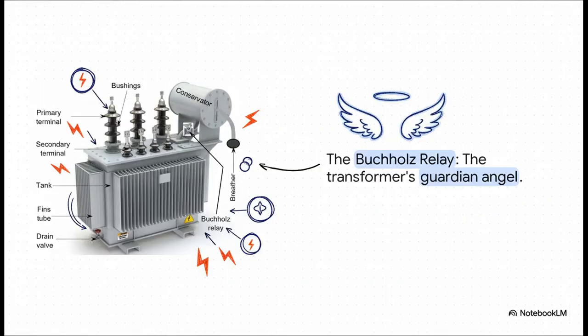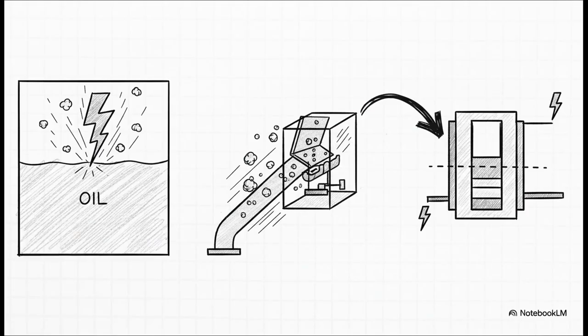But what happens if something goes really wrong on the inside? For that, transformers have a guardian angel called the Buchholz relay—an absolute lifesaver. It's a safety switch that works with gas. If there's a massive internal fault, like a big electrical spark, the intense heat boils the oil around it, creating a sudden burst of gas that rushes upward. The Buchholz relay detects that flow and instantly trips a circuit breaker, shutting the whole transformer down before it can destroy itself.